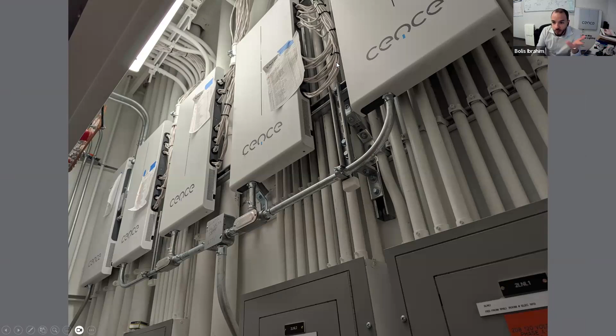Sorry, before we get too far, a question from Mark. Is there a specific type of wire that's employed in these types of installations? For example, Cat 1. Is the wiring plenum rated? So, good question. Specific type of wire, not really. There's so many different types of wire. These are low voltage, so 16.2, or sorry, 14 rather. These are 14.2 plenum rated cables because they are going in the return air plenum.